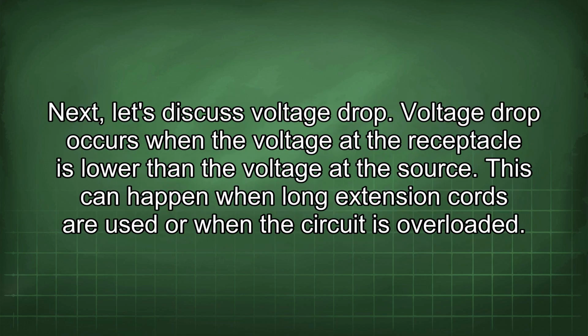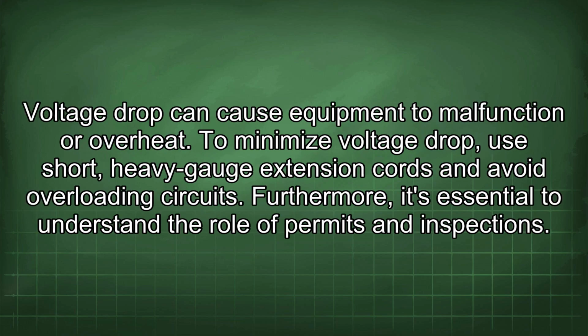Next, let's discuss voltage drop. Voltage drop occurs when the voltage at the receptacle is lower than the voltage at the source. This can happen when long extension cords are used or when the circuit is overloaded. Voltage drop can cause equipment to malfunction or overheat. To minimize voltage drop, use short, heavy-gauge extension cords and avoid overloading circuits.